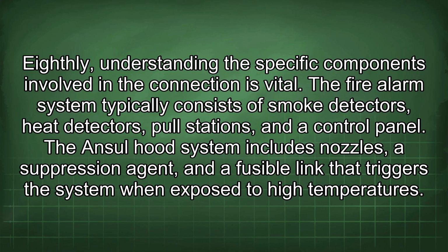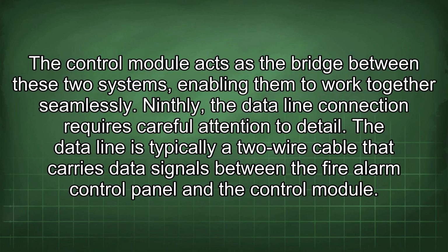Eighthly, understanding the specific components involved in the connection is vital. The fire alarm system typically consists of smoke detectors, heat detectors, pull stations, and a control panel. The Ansul hood system includes nozzles, a suppression agent, and a fusible link that triggers the system when exposed to high temperatures. The control module acts as the bridge between these two systems, enabling them to work together seamlessly.